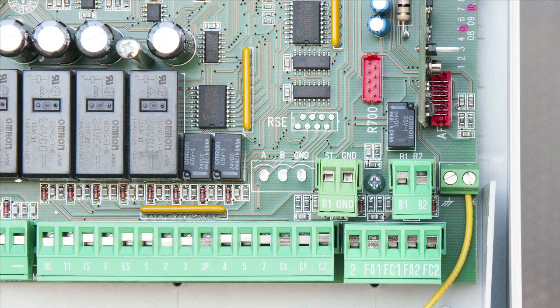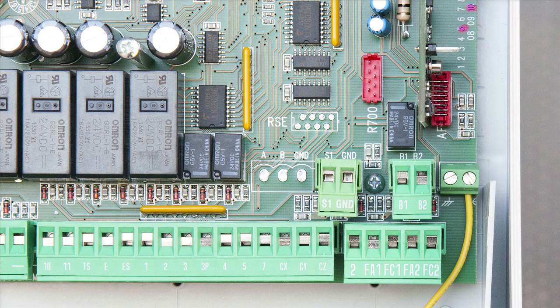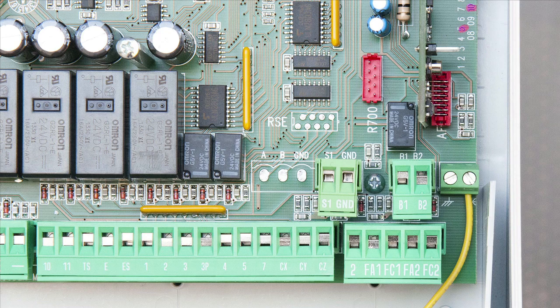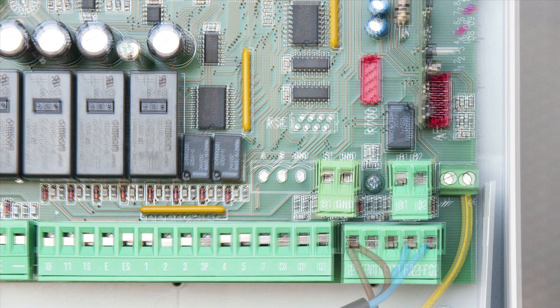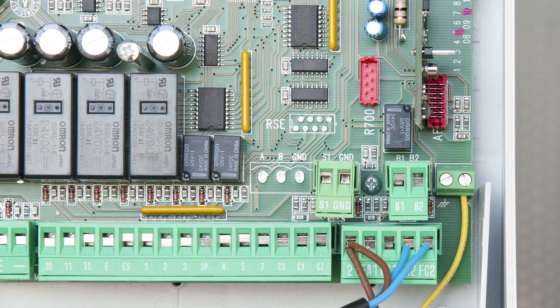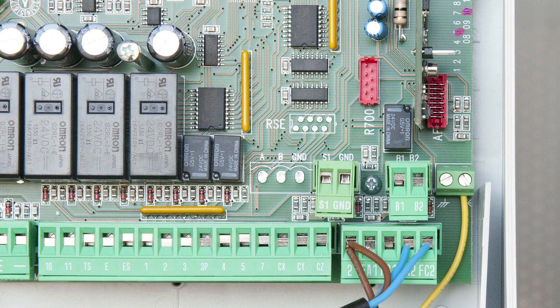To set up limits, connect both brown wires from the switches to terminal 2 on the right side of the control board. Connect the blue wire that is from the switch at the open limit to terminal FA2. Connect the blue wire that is from the switch at the closed limit to terminal FC2.